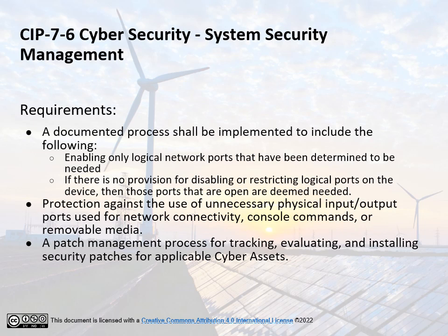CIP-007-6 System Security Management. Requirements: A documented process shall be implemented to include the following: enabling only logical network ports that have been determined to be needed, including port ranges or services to handle dynamic ports. If there is no provision for disabling or restricting logical ports on the device, then those ports that are open are deemed needed. Protection against the use of unnecessary physical input or output ports used for network connectivity, console commands, or removable media.